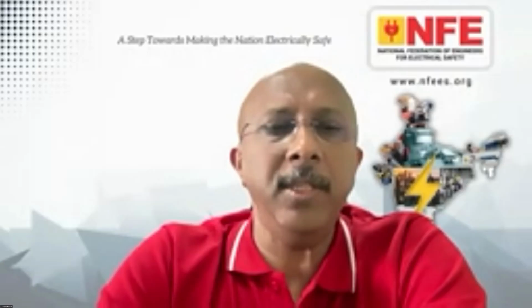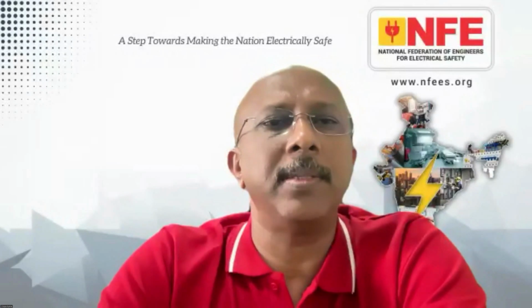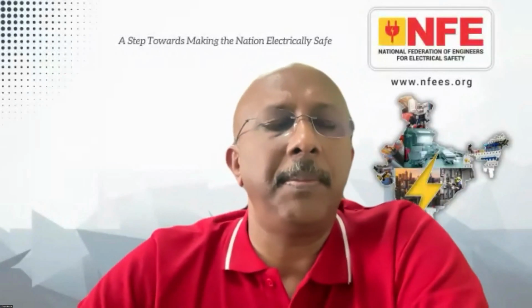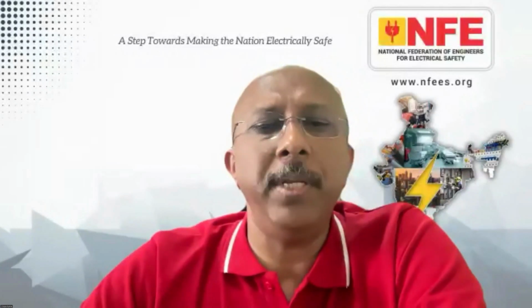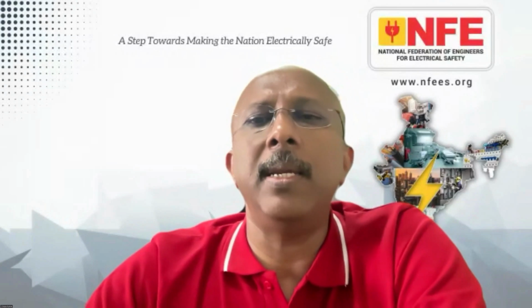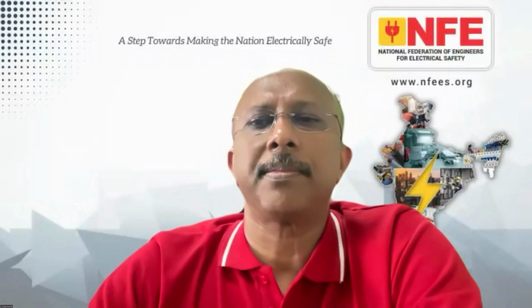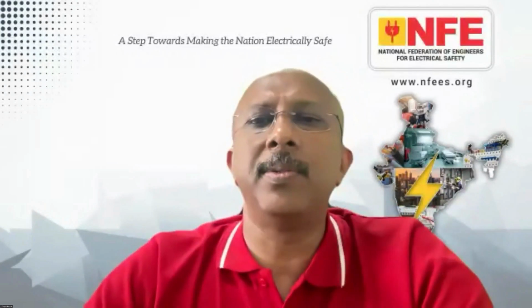Jay Kumar Gupta, please clarify what is the substitute for bare conductor used for earthing in flammable material tank farm storage, or other parts of operational hydrocarbon processing plants. Insulated and continuous conductors. That means minimum joints, continuous conductor, and insulated. Okay, I had that answer.